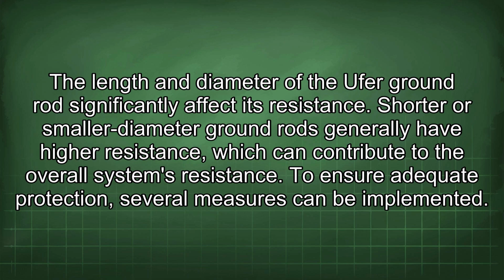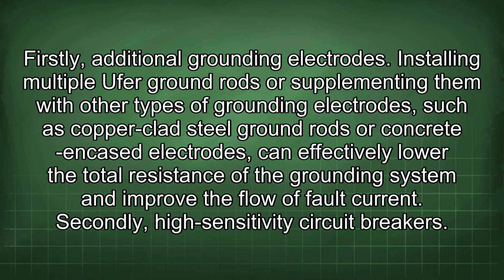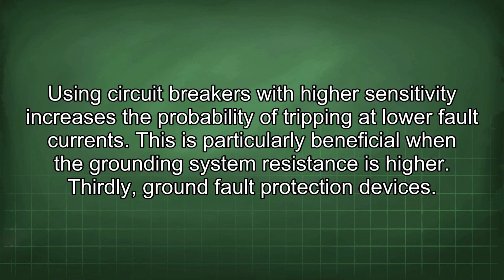To ensure adequate protection, several measures can be implemented. Firstly, additional grounding electrodes. Installing multiple Ufer ground rods or supplementing them with other types of grounding electrodes, such as copper-clad steel ground rods or concrete-encased electrodes, can effectively lower the total resistance of the grounding system and improve the flow of fault current. Secondly, high-sensitivity circuit breakers. Using circuit breakers with higher sensitivity increases the probability of tripping at lower fault currents. This is particularly beneficial when the grounding system resistance is higher.